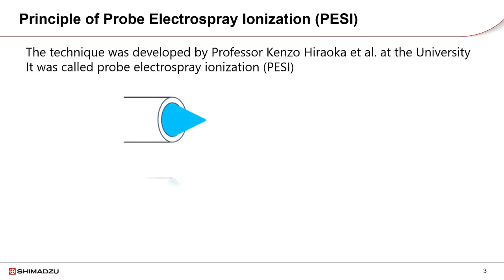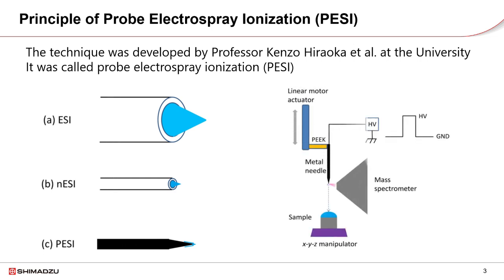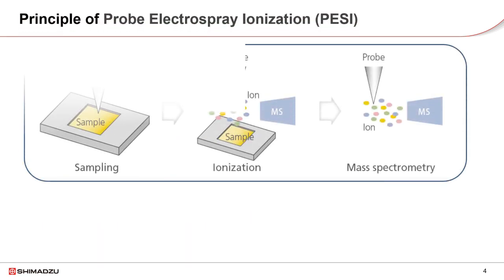This new ionization technique was developed by Professor Kenzo Hiraoka at the University of Yamanashi in Japan. The technique is called Probe Electrospray Ionization, or PESI. The probe is a sharp metal needle moving up and down during analysis. It touches the sample and brings sample material up, and a high voltage is applied that causes electrospray ionization to occur.